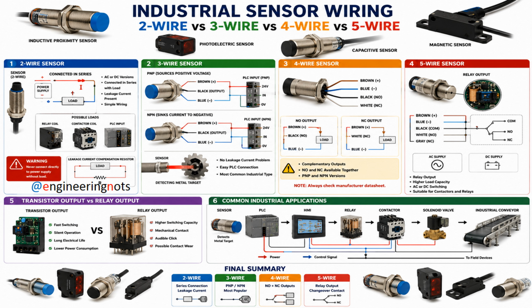But the important point is this. A sensor does not perform any action by itself. It only generates information. This information may be sent to a PLC, a relay, a contactor, an HMI, a controller, or an input module.